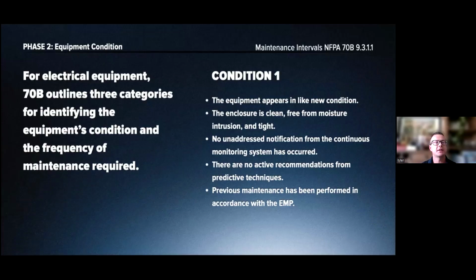For electrical equipment, 70B outlines 3 categories for identifying equipment condition and the frequency of maintenance required. Condition 1 is the appears-like-new condition, which can apply to a lot of your facilities - I know we're pretty much at a place where life expectancy has exceeded 30 years, but a lot of equipment can still be in very good condition. The enclosure is clean, free from moisture intrusion, and tight - that's another thing to be mindful of and make sure is maintained. There's no active recommendations from predictive techniques, and preventive maintenance has been performed according to the electrical maintenance plan.